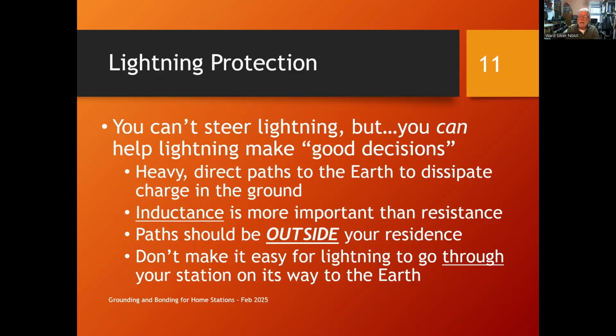What does lightning want? Lightning wants a heavy, direct path to the earth to dissipate this charge imbalance in the ground. So the charge is going to spread out and go into the ground, or it's going to come from the ground and flow up through the strike to where there's less charge, and so it equalizes the charge imbalance. It wants a heavy, direct path. Okay, remember we talked about lightning goes from DC to way up in the UHF spectrum. So it's an RF event. It's an AC event. And in that case, inductance is more important than resistance. AC safety, you want low resistance. In lightning protection, you want low inductance, okay? The voltage across a conductor is proportional to its inductance.